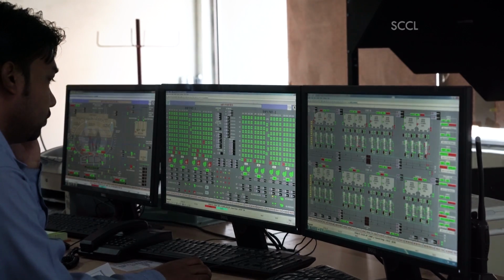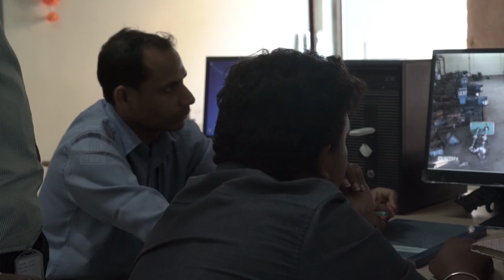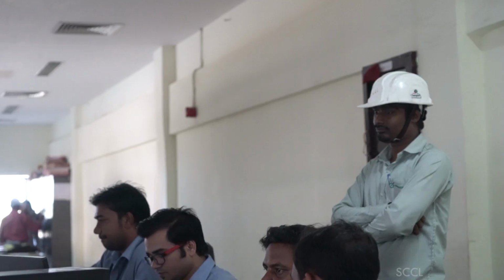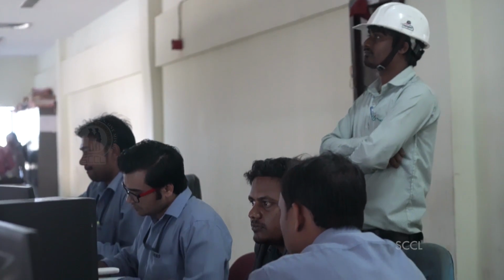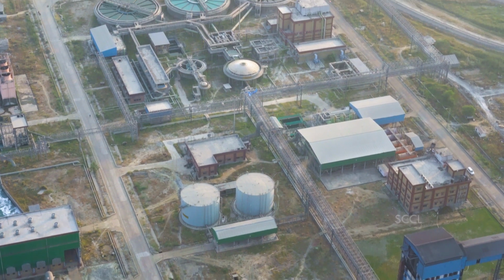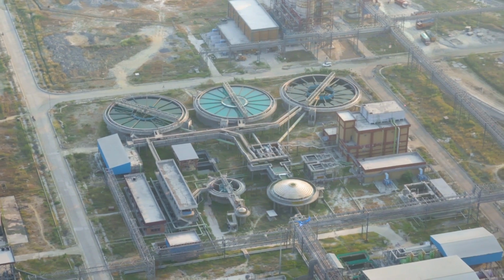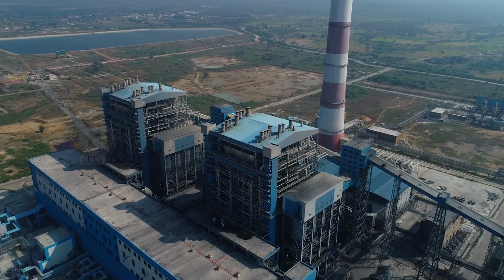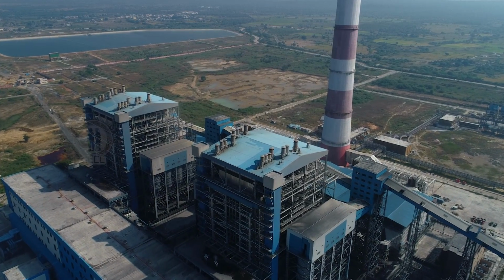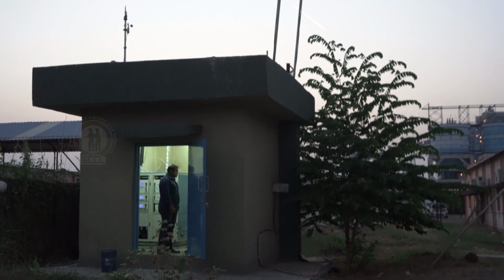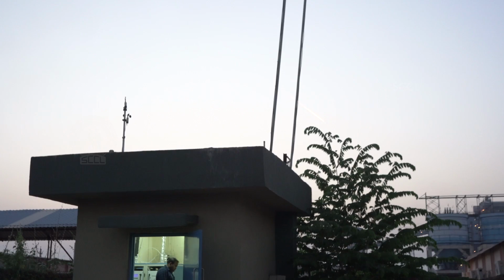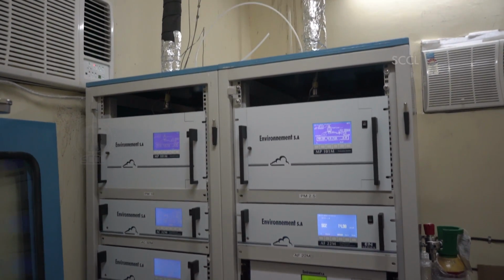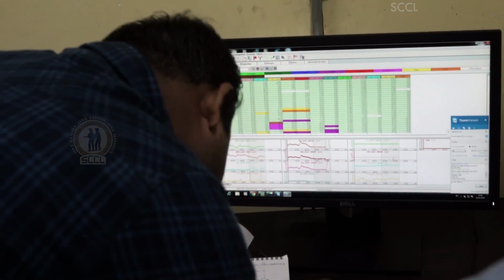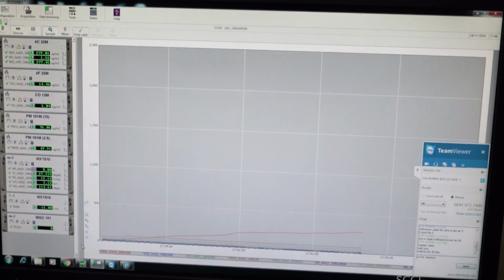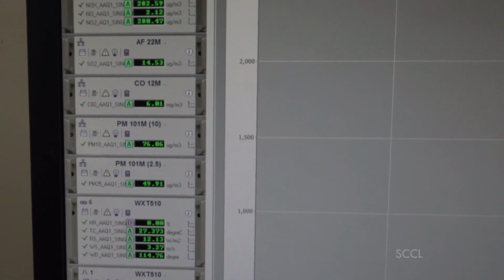Apart from the control room, there are coal handling plant and ash handling plant control room operations controlling the coal flow and ash evacuation. Water chemistry is closely monitored by the demineralization plant's team all through the day, as water chemistry will have a lot of impact on the boiler and turbine performance. STPP is equipped with CEMS, Continuous Emission Monitoring System, to monitor sulfur oxides, nitrogen oxides and particulate matter called fly ash. All the data collected is being constantly monitored by various state and central government authorities.